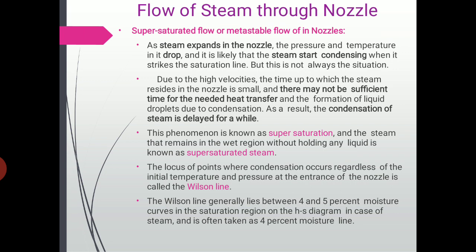Due to high velocity, the time the steam resides in the nozzle is small. This is very important: there may not be sufficient time for the needed heat transfer and the formation of liquid droplets due to condensation. As a result, the condensation of steam is delayed for a while.